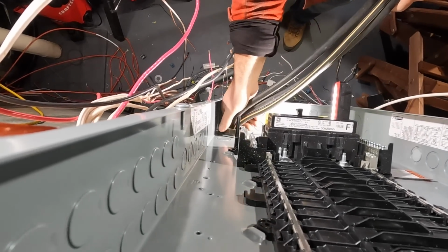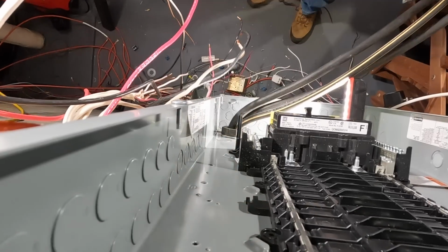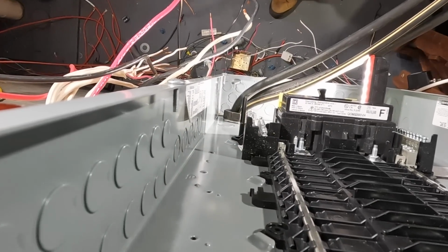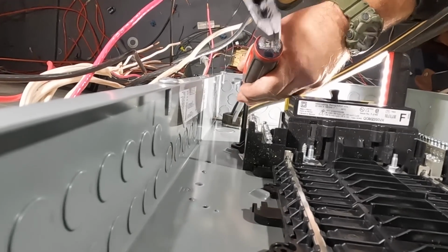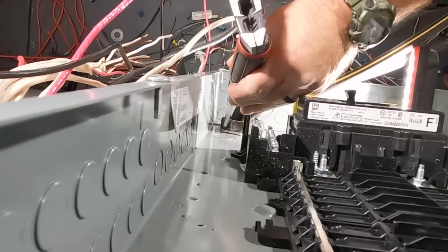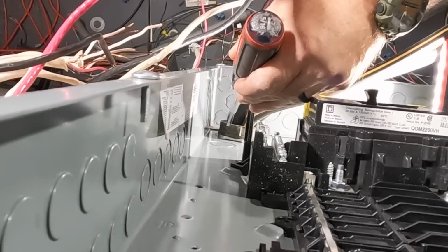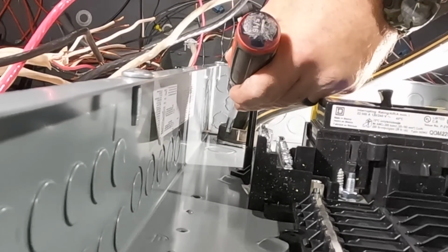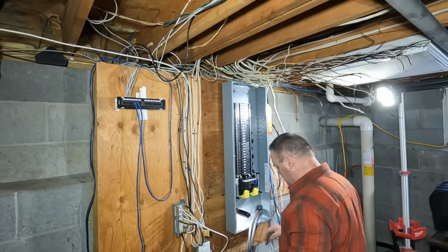Always don't forget to put the insulating bushing on here. This is important so you don't damage the insulation on the conductors. If you put it on last after pulling the conductors, you've defeated the purpose. Please remember to put your bushings on before you pull the conductors.